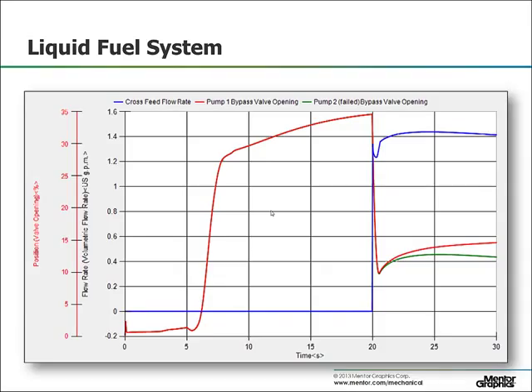We can also look at the bypass valve openings as a function of time, along with the cross-feed fuel flow rate in blue. You can see again at the 20-second mark, the pump stops and the flow rate jumps from the bottom side of the model to the top. And also the bypass valves close to maintain pressure. One pump is slightly higher than the other because of the pressure drop in the bypass line.